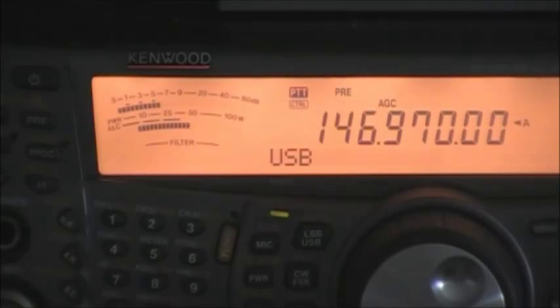Turn the volume up a little. Actually, before I do that, I want to mention you have to do this in single sideband mode. If you have this problem and you're checking 2 meters, don't do it in FM—you won't hear the static. You might see the S meter indication, but it might be so subtle you won't notice. The arcs create an amplitude modulated source of RF, not frequency modulated, so you won't hear it in FM mode like you do in single sideband. You could also listen in AM mode, but single sideband gives the best audible indication. So we'll turn the volume up.